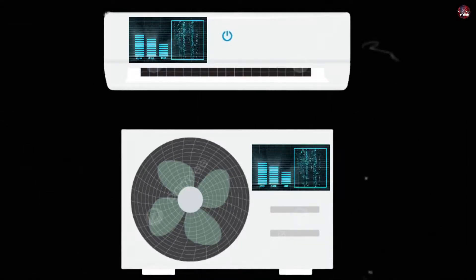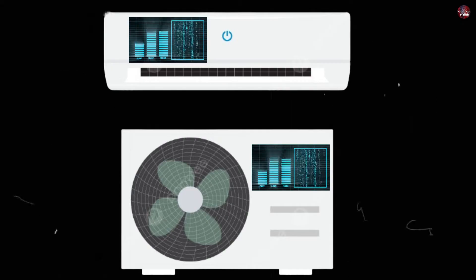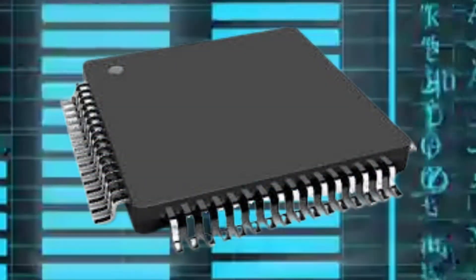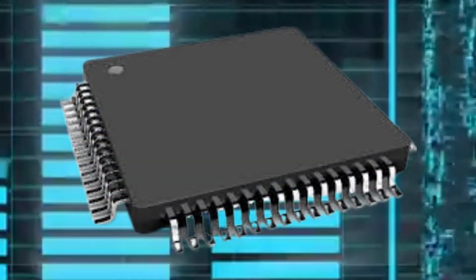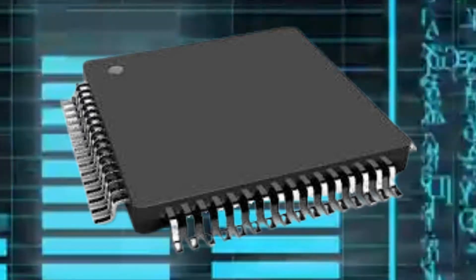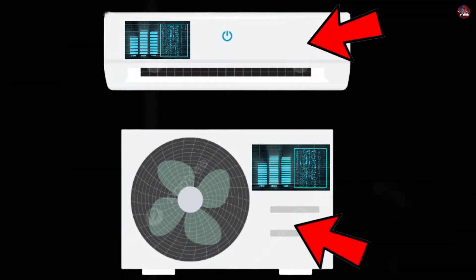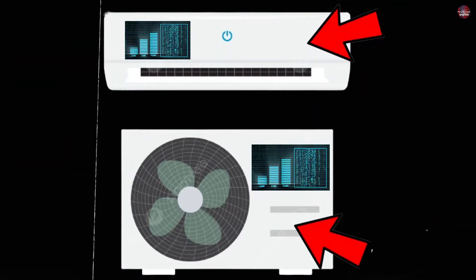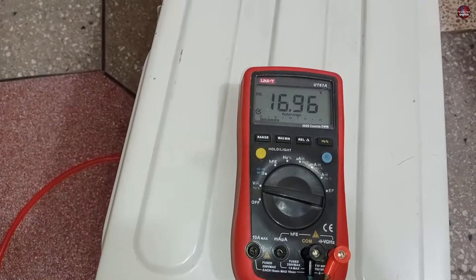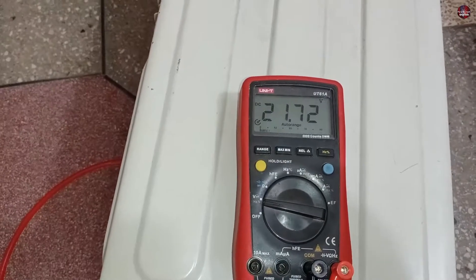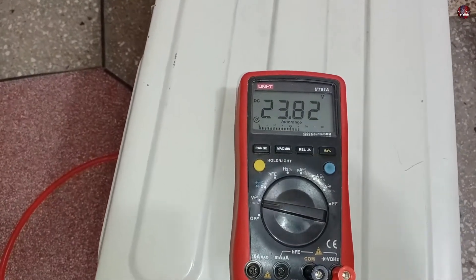Both units are coded in such a way that they should receive the same fixed voltages that are programmed in their microcontrollers. This is how they understand each other and what is going on in the indoor and outdoor unit circuit boards. This voltage fluctuation is the language through which the indoor and outdoor units communicate.